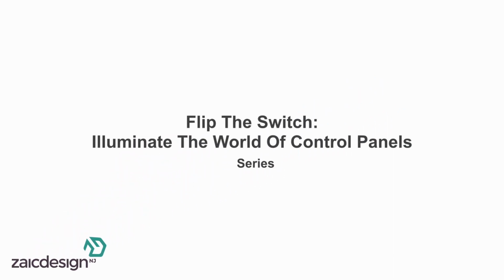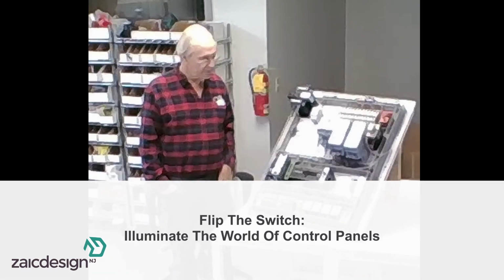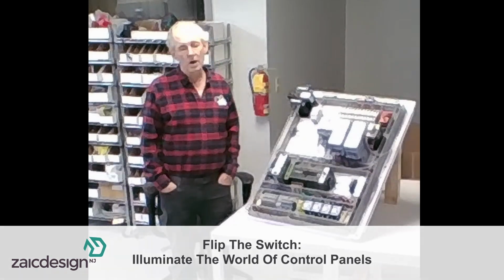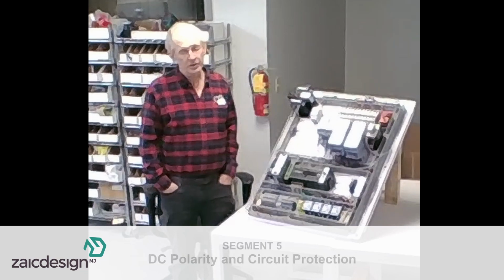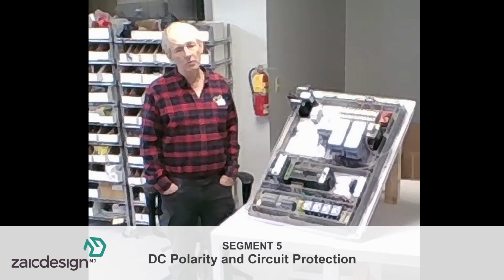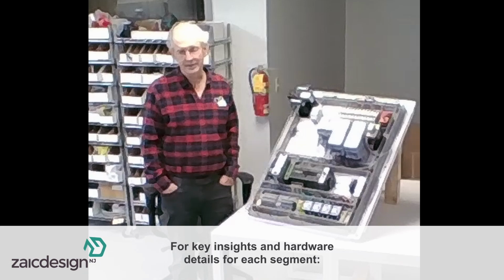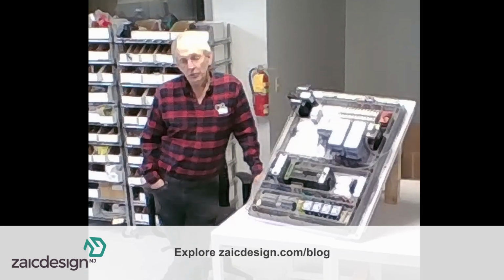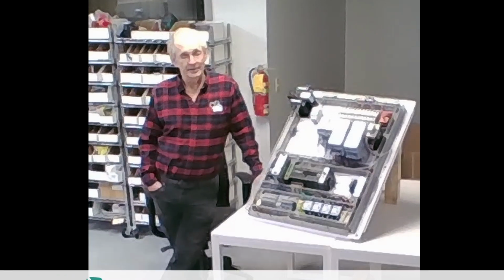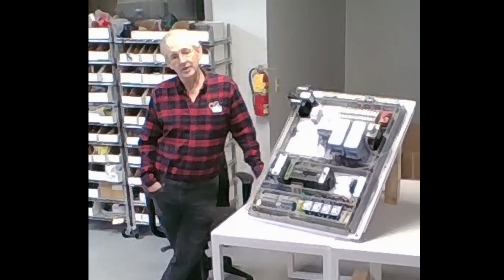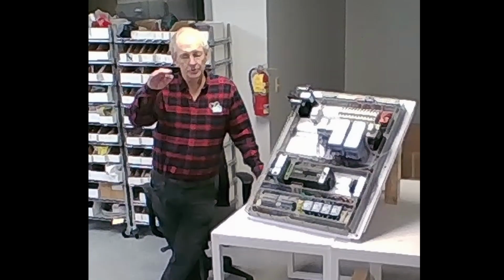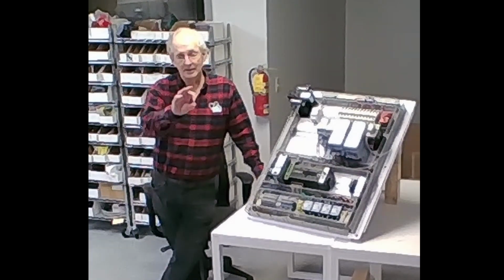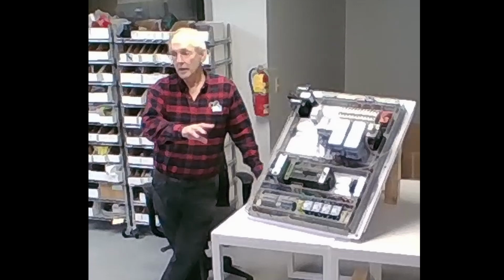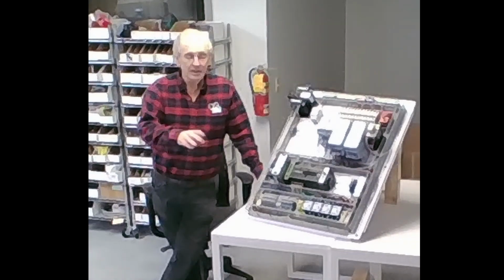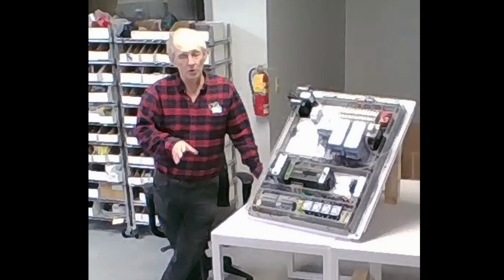In DC we have polarity. And there are two ways of switching DC electronically. One's called sinking and the other's called sourcing. The reason there's two different kinds is that originally they couldn't build a transistor that was sourcing. They could only build a transistor that was sinking. In other words, it would take a voltage and pull it down to ground. Those were NPN transistors. And we didn't get PNP transistors for a long time.